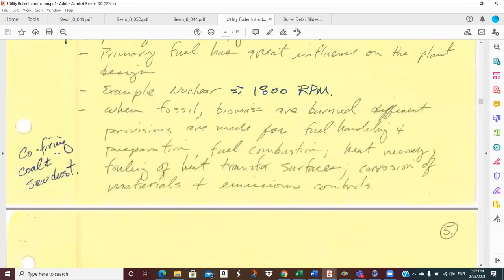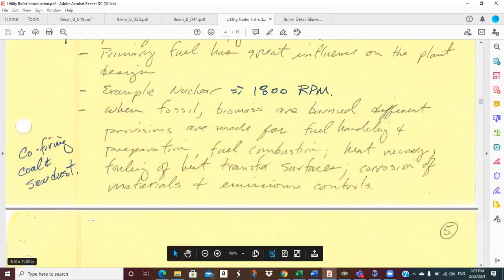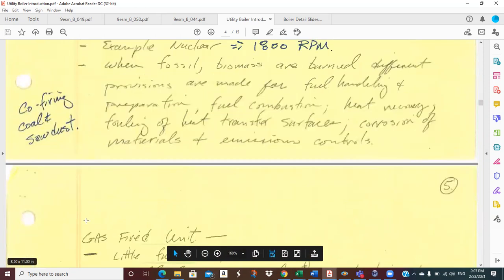TVA back in the day, before they decided to basically move away from these coal units, they tried all kinds of co-firing tests. They did some co-firing with sawdust. So they would take sawdust and mix it in with the pulverized coal and run that into the burners. And I think they could run up to like 15-20% of the heating value of the fuel as sawdust, which in some cases was being landfilled. In a lot of cases, people can find places to take sawdust, but sometimes not, and it's not economical. And so it'll wind up landfilled. Anyway, TVA gave that a shot, but they never did it permanent.